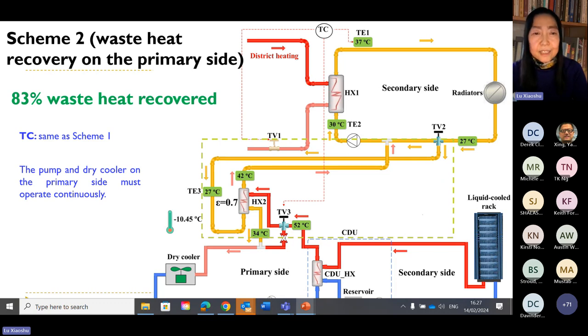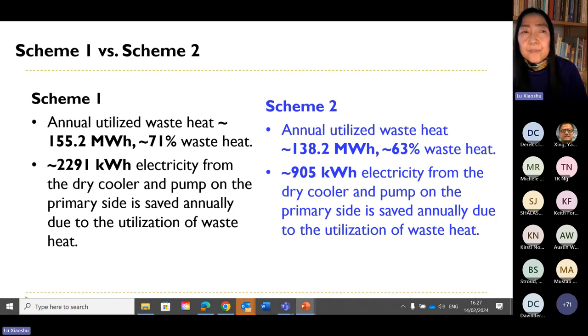I think you can discover that the dry cooler and the pump on the primary side must run all the time. So this is the result. Scheme one can utilize waste heat of about 150 megawatt hours, equivalent to 71% of annual waste heat. Additionally, it can save about 2,291 kilowatt hours of electricity for the dry cooler and pump on the primary side. The corresponding values are a bit lower in scheme two.